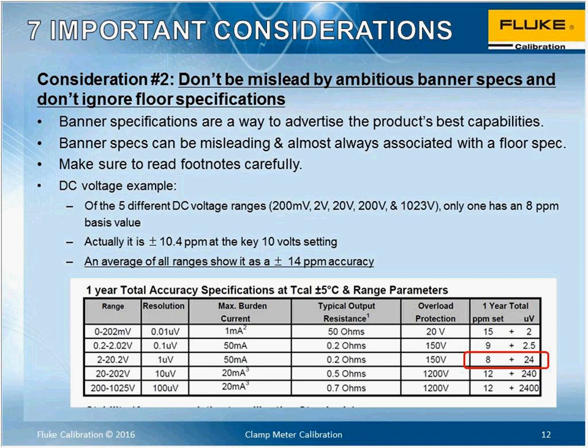What we show is a specification where the manufacturer claims to have 8 ppm as their banner spec. But when we look at that 8 ppm spec, what we'll see is that it's only for one range. And if you really look at the range from 200 millivolts up to 1,000 volts, it's really an average of 14 parts per million accuracy. And in some cases, it has a pretty aggressive floor spec. So the takeaway here is, when evaluating a product, look at its entire spec range. Don't go off banner specs.